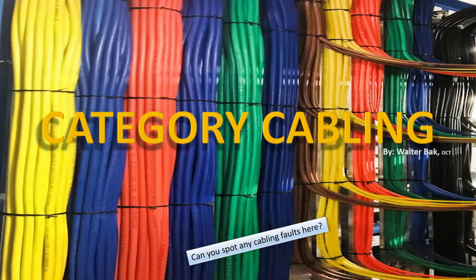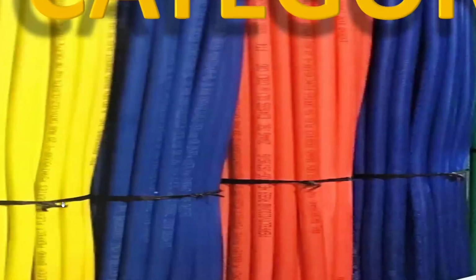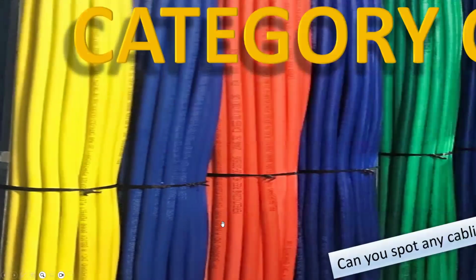It's not easy to spot if you're not in the topic just yet, as far as the experience and so on. Notice how these bindings look like some sort of twisties or something like that. Look as they are deforming the cable, they are squishing the cable. Cables are not supposed to be squished.